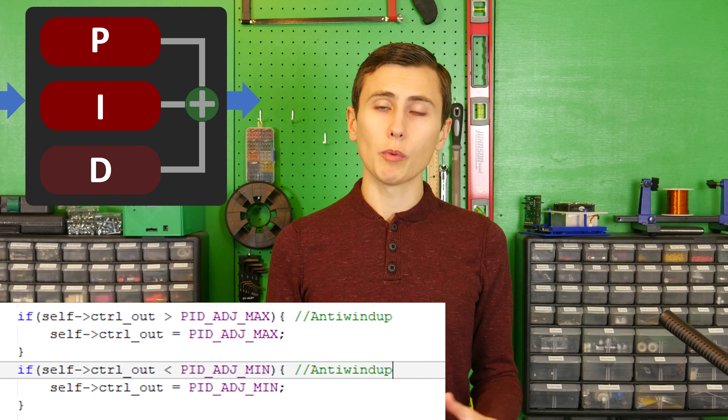However, for our UPS, we wanted to give our controller a little more leeway in case the output of the inverter becomes overloaded. We allowed a certain quantity of clipping in our voltage waveform — in this case 20%. This means that the output of the UPS will allow the output waveform to clip just a little bit if overloaded to increase the maximum power passed into the load. The alternative would be allowing the output of the UPS to brown out. Clipping means there will be some higher frequency harmonics that may come out of the inverter when overloaded, but it just might allow our connected device to hold on just long enough to finish shutting down safely.